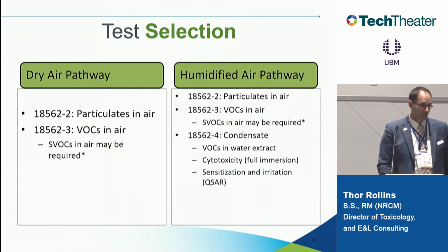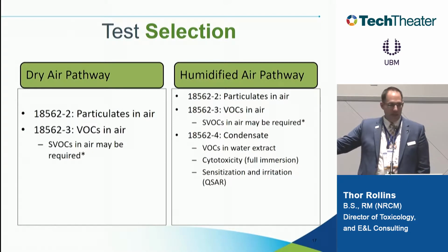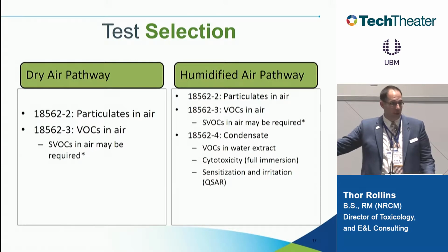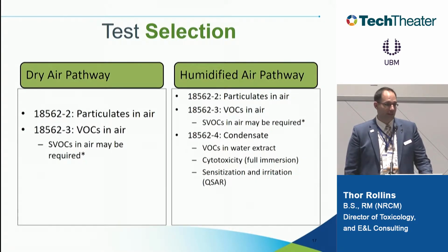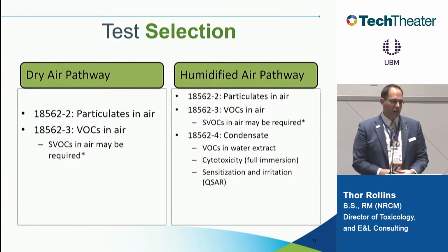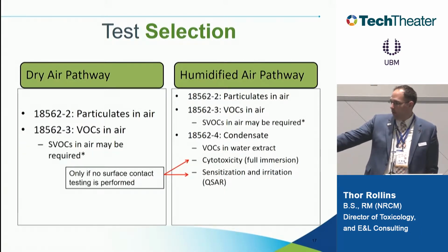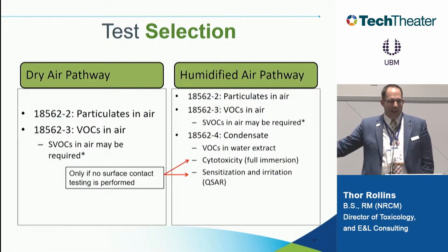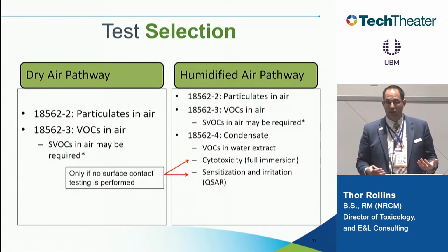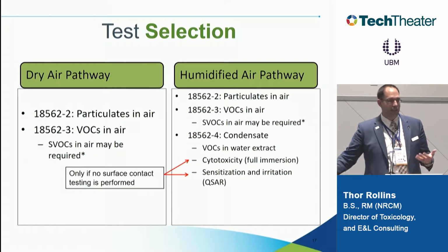So if your gas path device does not contact the skin in any other way, then yes, we would be able to use this instead of doing the sensitization and irritation tests. If you have a mask that contacts the skin, then that part would have to go through the traditional biocompatibility tests. And just so you know, only if no surface contact, that was a segue, good job. So this has actually been very successful for us. We've done this with the FDA in the last 4 or 5 months and have been able to successfully argue that this is a good approach for these types of devices.